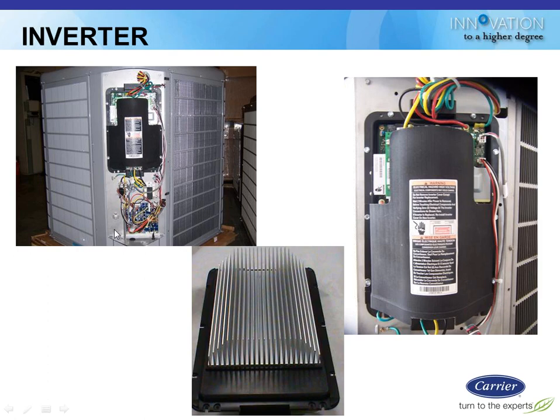If you took this whole section off, you would be able to get into some of the components like the expansion valve and the reversing valve. The inverter is the top half guy there with the black cover on him. And down in the bottom you see a picture of what it looks like on the back side with all those fins. That's to dissipate heat away from the inverter to keep it cool.